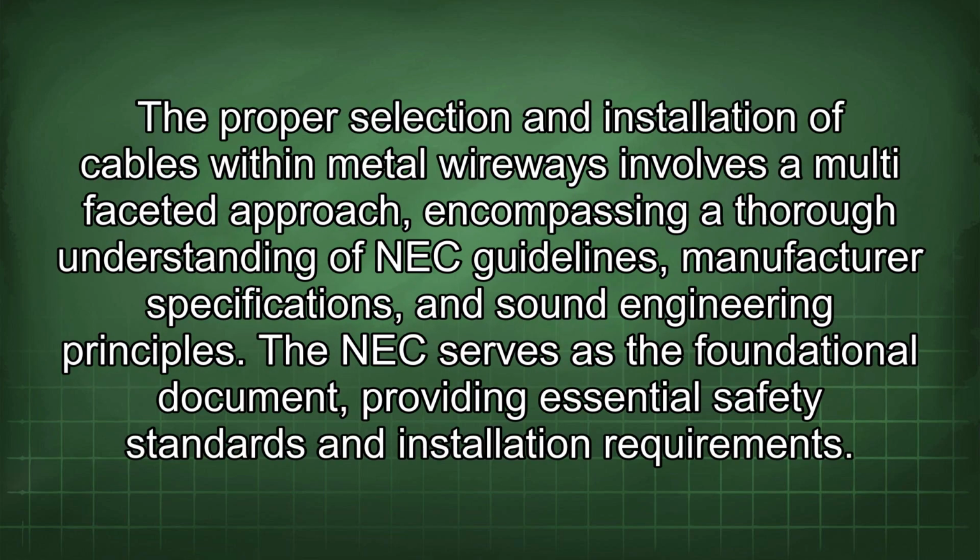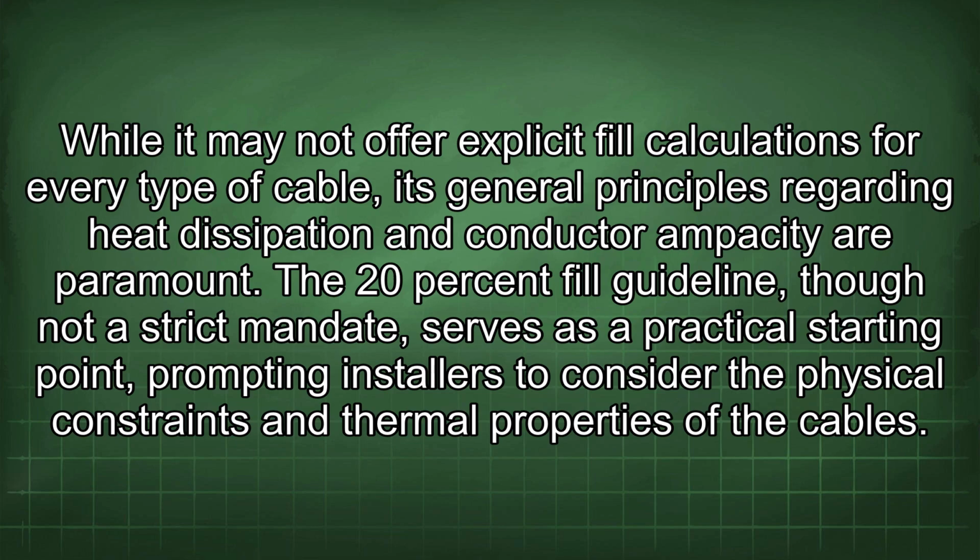The proper selection and installation of cables within metal wireways involves a multifaceted approach, encompassing a thorough understanding of NEC guidelines, manufacturer specifications, and sound engineering principles. The NEC serves as the foundational document providing essential safety standards and installation requirements. While it may not offer explicit fill calculations for every type of cable, its general principles regarding heat dissipation and conductor ampacity are paramount. The 20% fill guideline, though not a strict mandate, serves as a practical starting point, prompting installers to consider the physical constraints and thermal properties of the cables.